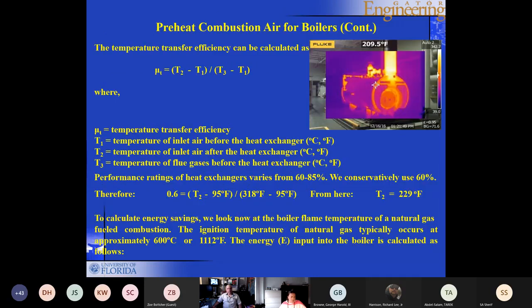If you look at the next slide, you could come up with what they call a transfer efficiency, or a temperature transfer efficiency. It can be calculated by this ratio, T2 minus T1 over T3 minus T1, T3 being the temperature of the flue gases before the heat exchanger. A conservative estimate for that ratio is somewhere between 60% and 85%, or 0.6 to 0.85. We're going to use the lower end, which is 0.6. And if that happens, then we can get the T2, which is the temperature of the air at the inlet after the heat exchanger, up to 229, up from the ambient temperature, which is 95 degrees.